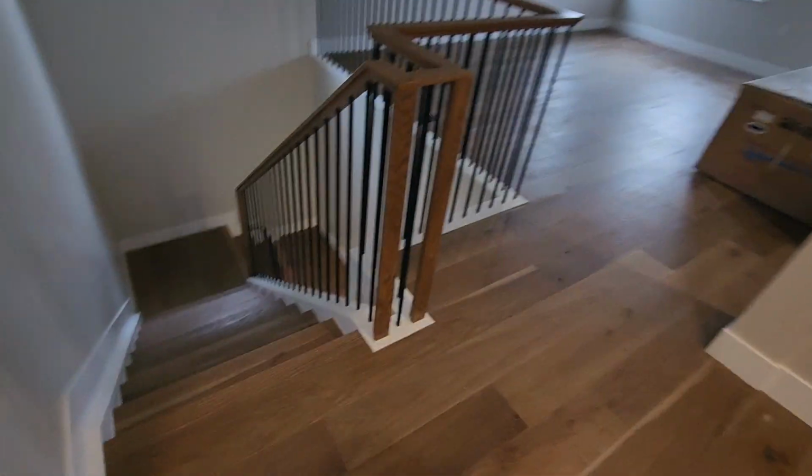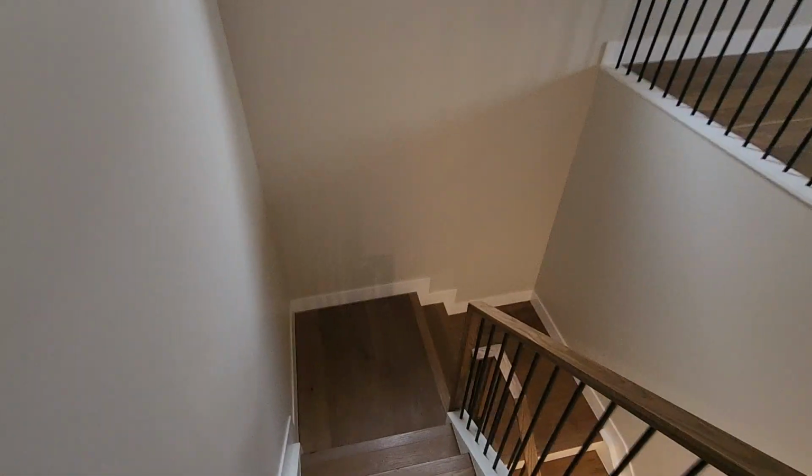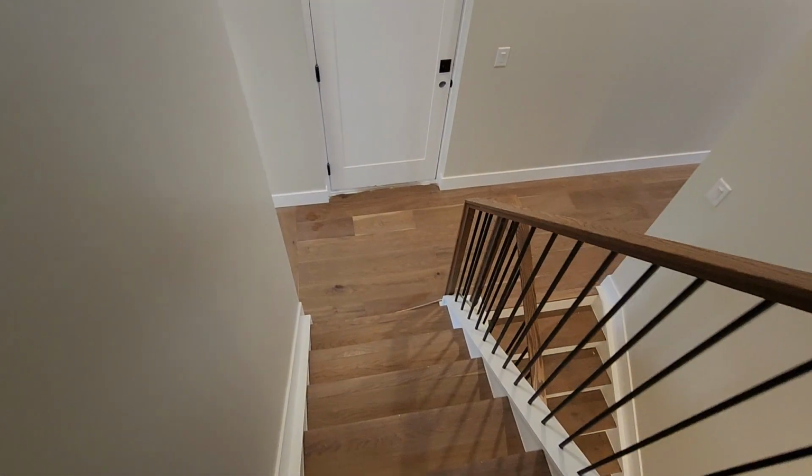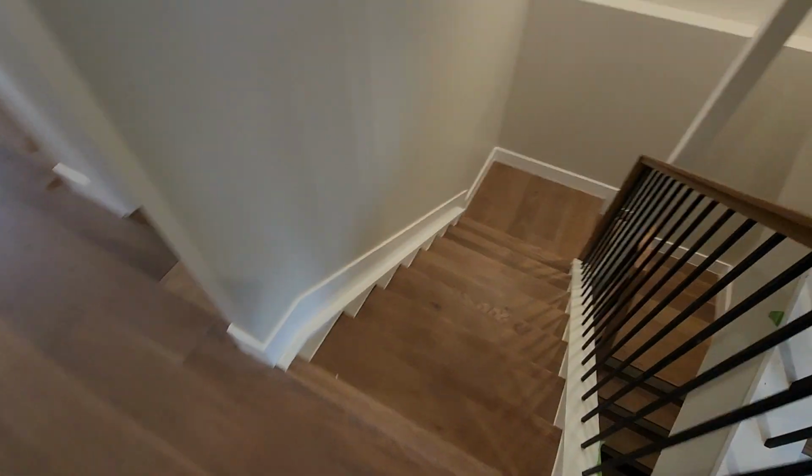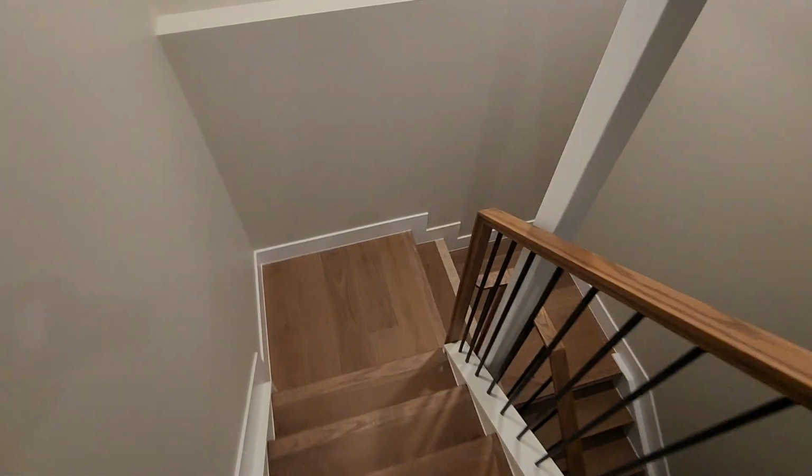But let's go downstairs and check out the ERV unit, which is the heart of a Passive House. It's the fresh air ventilation heat recovery unit, and it's also an enthalpy unit. That means that we are getting our moisture, our vapor, back into the house. I believe it's rated up to 70% humidity recovery. Colorado, especially in the wintertime, boy, does it get dry. So the more humidity we can recover, the better. We like to be at least 30%, preferably around 35 to 40%.